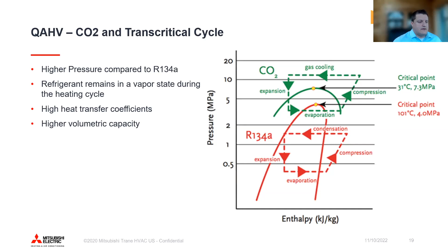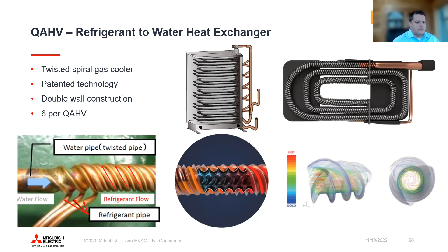Here's a picture of what those gas coolers look like. They are unique and patented as far as how they operate, but you can think of it this way: your bigger pipe here on the bottom left is your water pipe. You can think of a water pipe just twisted, and then we wrap around the different capillary tubes for the CO2. It really helps us get that high efficiency out of the heat exchange, lower pressure drop, but also that turbulent flow throughout the heat exchanger.